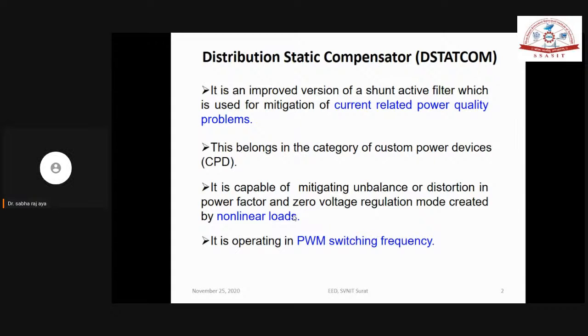Okay. Again, this whole system is going to operate in PWM mode only. Means maybe you can operate at a frequency not more than 5 to 10 kilohertz. We are not going to use 30 kilohertz, 40 kilohertz. 5 to 10 kilohertz is sufficient for turning on the IGBT if the converter is going to work as a DSTATCOM. Okay.